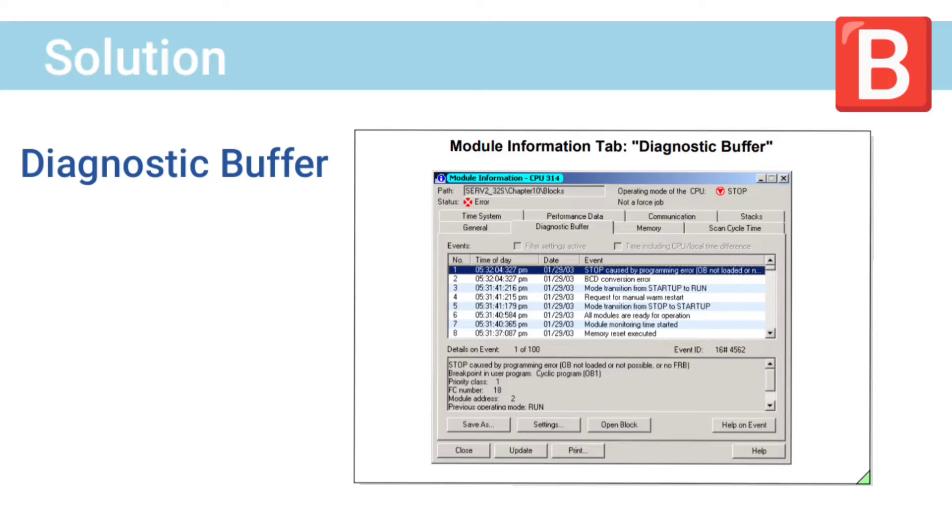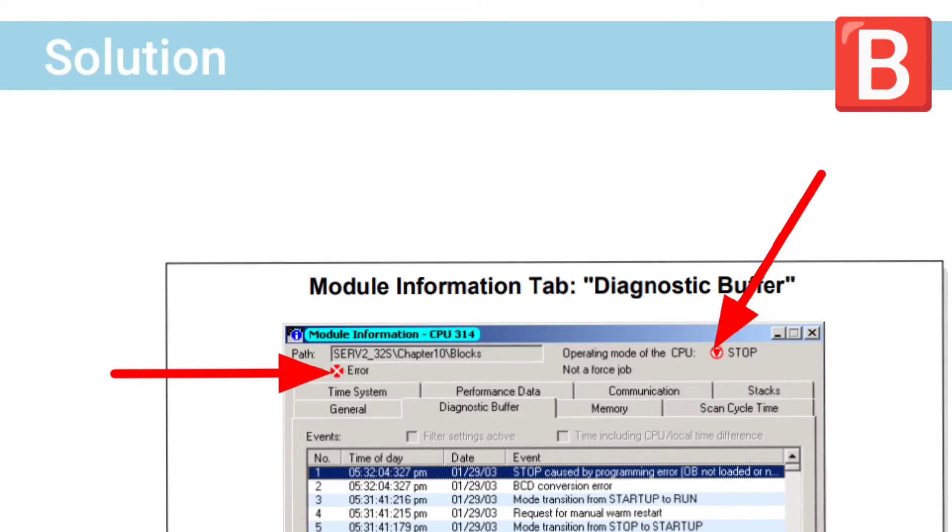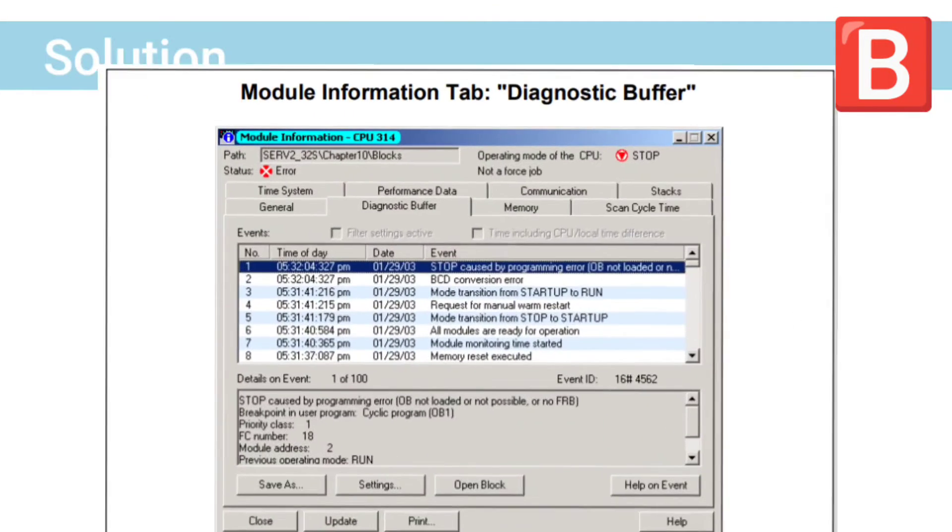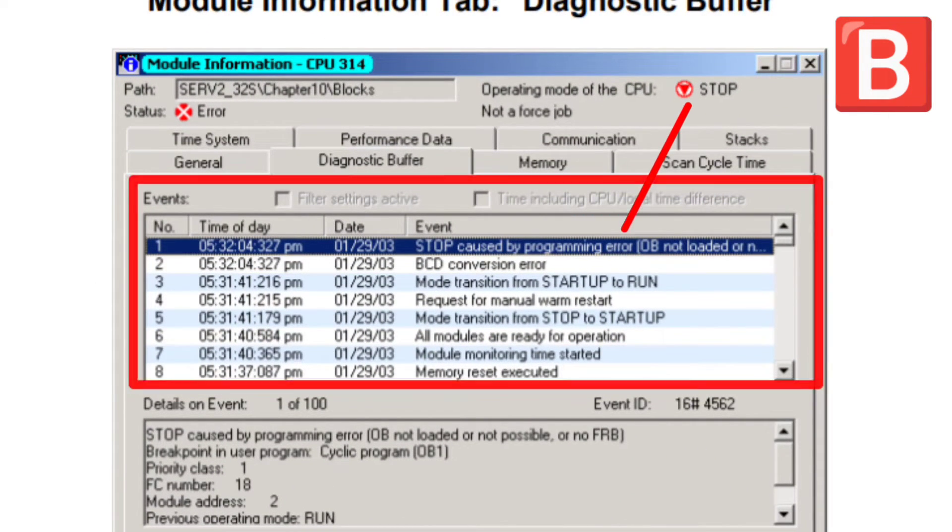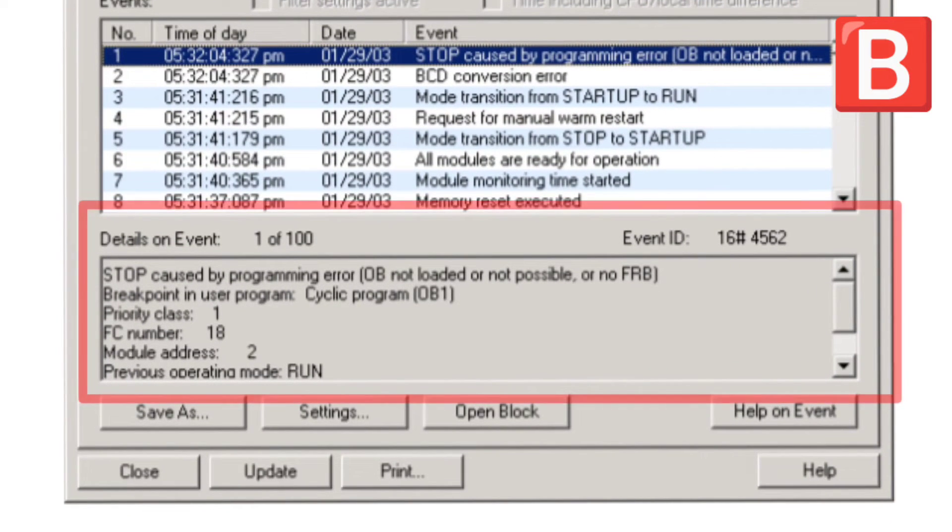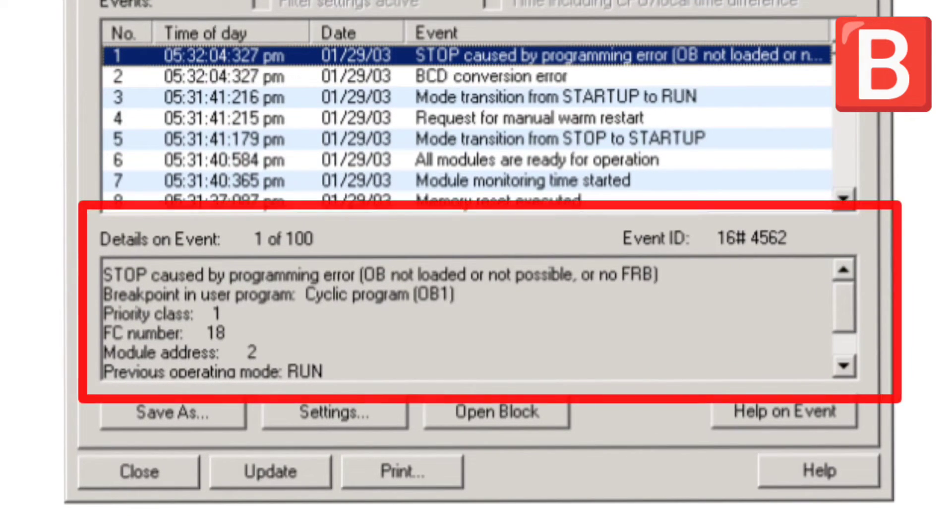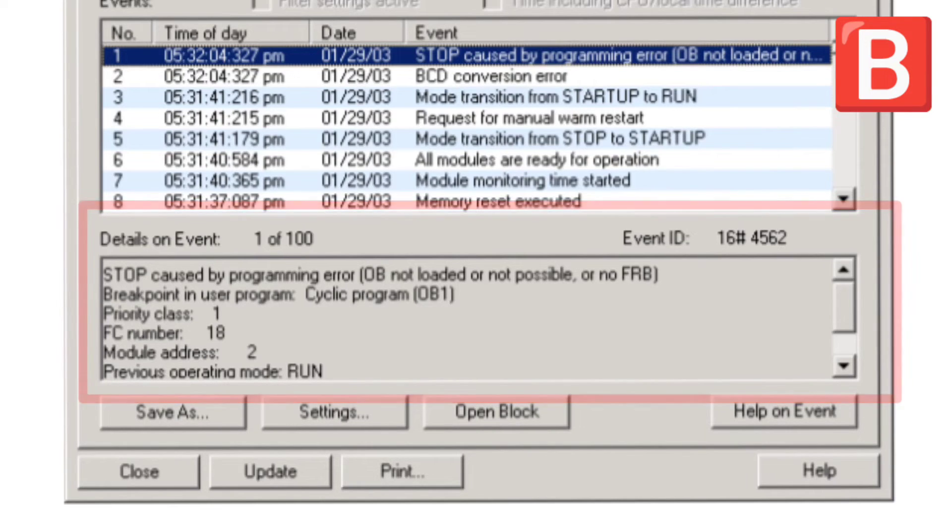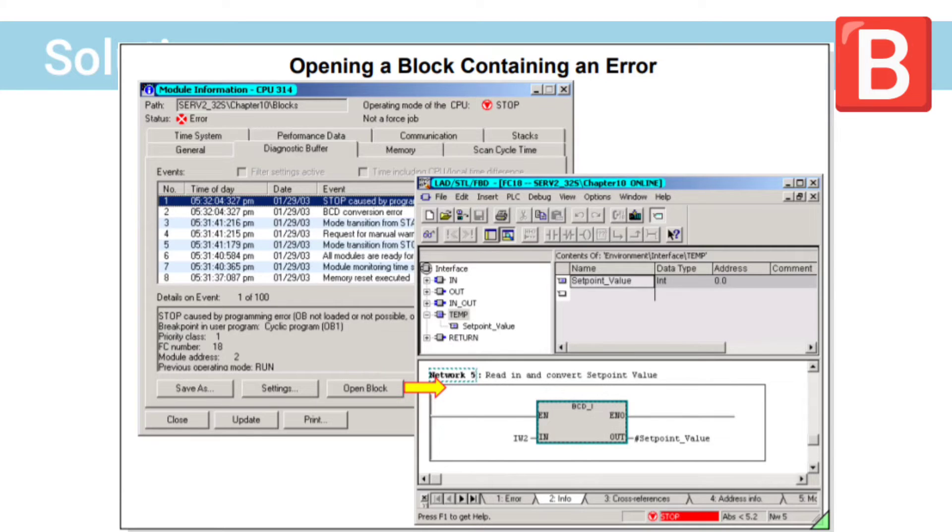There are two indicators to show the CPU status. Diagnostic buffer consists of an events window that shows events that happened to your CPU. In details on event, you can know why your PLC stopped in details. If you double click on open block, it will show the error block.